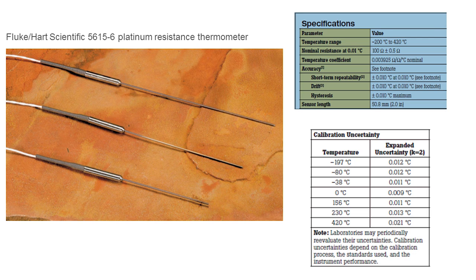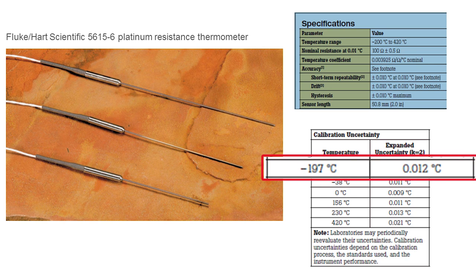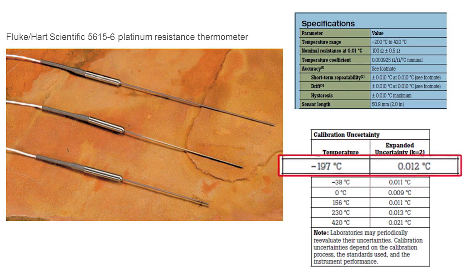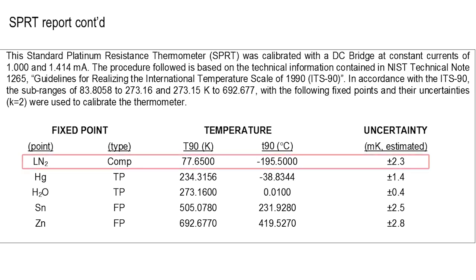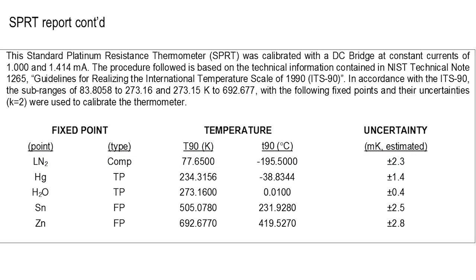As we look at a sample reference thermometer from Fluke or Hart Scientific, you're seeing that the expanded uncertainty from the manufacturer is as small as 0.012 degrees C. So it's highly accurate, very low uncertainty. With these temperature primary standards that we have, we are able to measure down to as small as 2.3 millikelvin degrees, or in other cases even smaller than that. So we're talking about very, very good accuracy, very low measurement uncertainty.